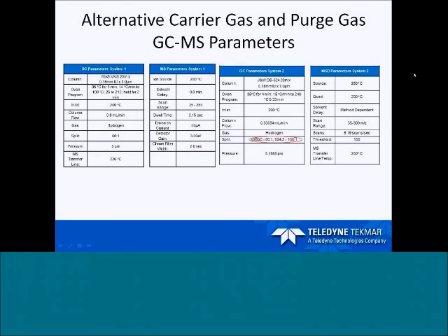On the second GC system, we used a slightly different method. The only difference was with 8260, we used an 80:1 split ratio, and for 524.2, we used a 150:1 split ratio. This is just due to the fact that for 524.2, we used a 25 ml sample volume.